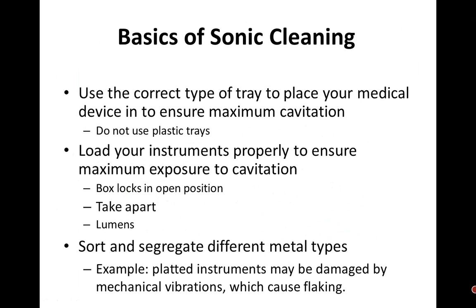So again, as with anything, you don't mix metals. Know the type of metal of the instrument that you have, and many times the IFU will say do not put in a sonic cleaner. So again, sort and segregate, know what's going on. Where do you get that information? I might sound like a broken record, but it's back to the instructions for use. The manufacturer who designed that instrument knows what's best and the best way to clean it. They have done the validation, and that's what's very important.